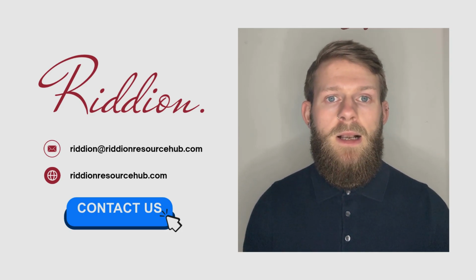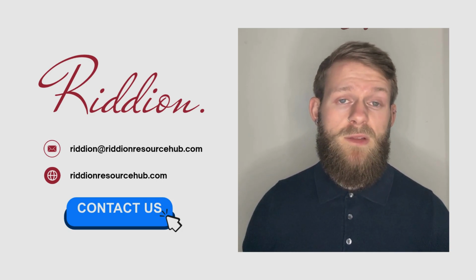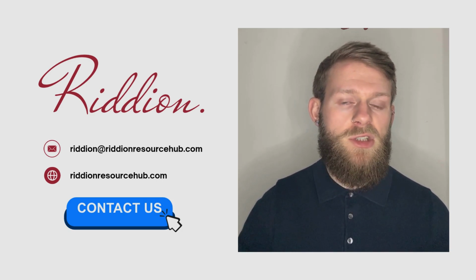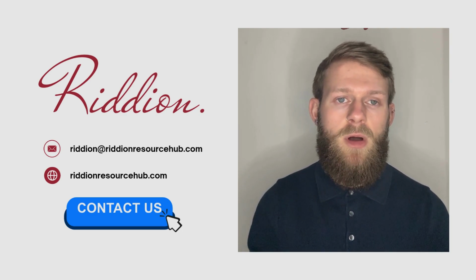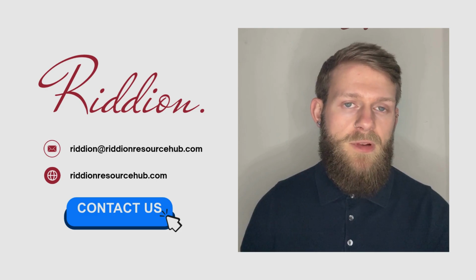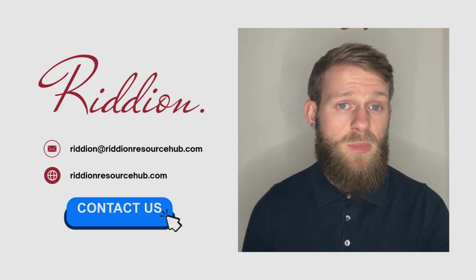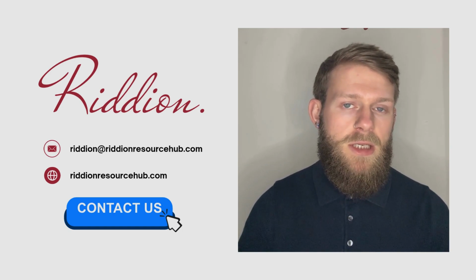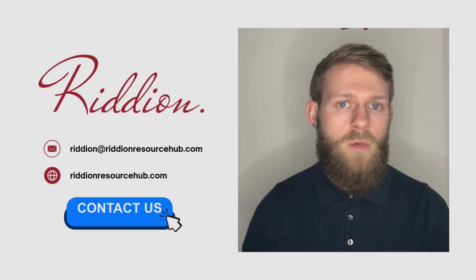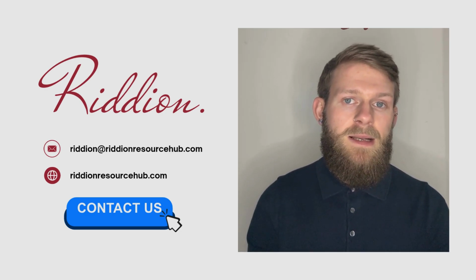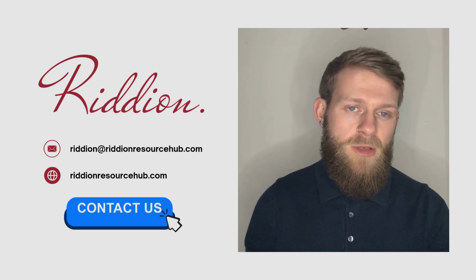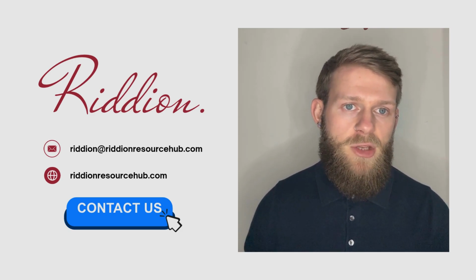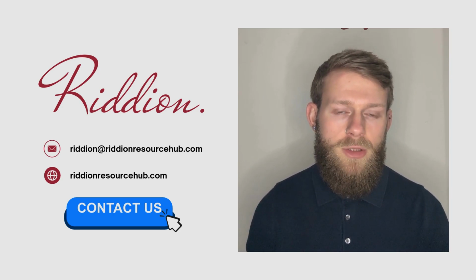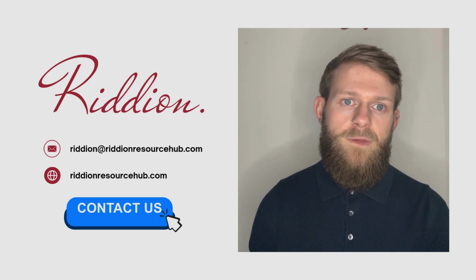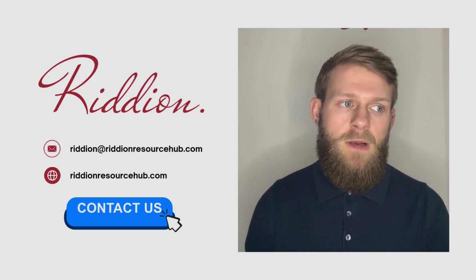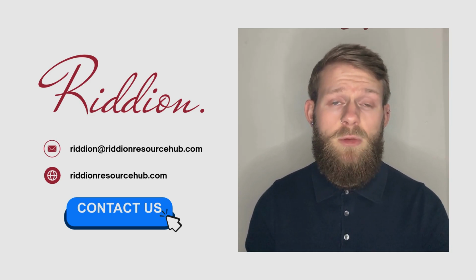Moving on to last but not least, ISO 13485 and UKCA marking in the United Kingdom. Since Brexit, the UK has introduced its own medical device regulatory framework, which requires manufacturers to obtain UKCA marking instead of CE marking. But ISO 13485 still remains the standard for QMS compliance in the UK. The MHRA continues to recognise ISO 13485 as the gold standard for medical device quality systems. And even though the UK is moving away from EU MDR, a 13485 certified QMS still plays a central role in UKCA approvals. So if you already comply with 13485 for EU MDR, your transition to UKCA will be smoother.